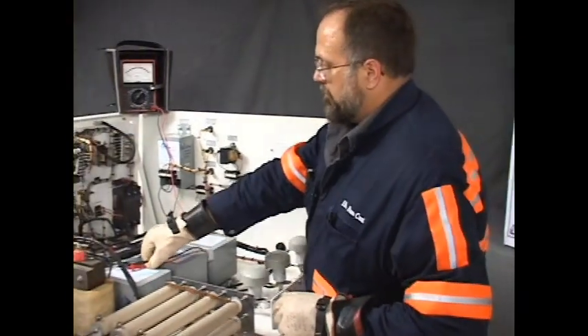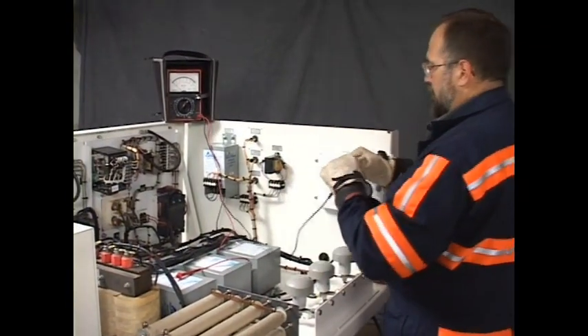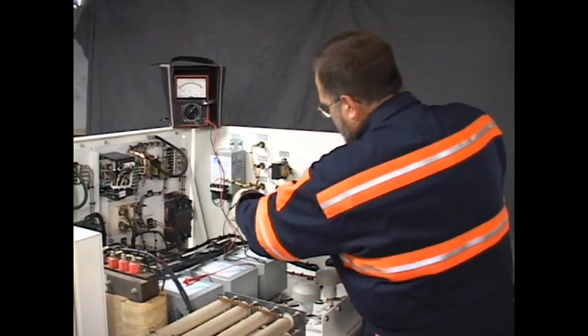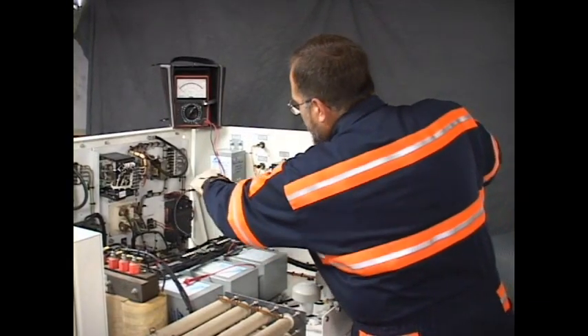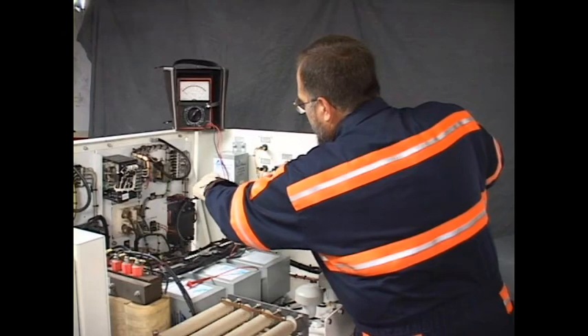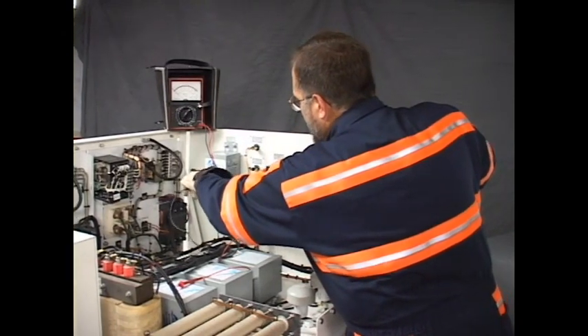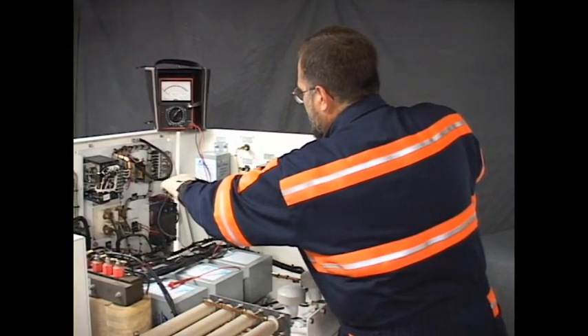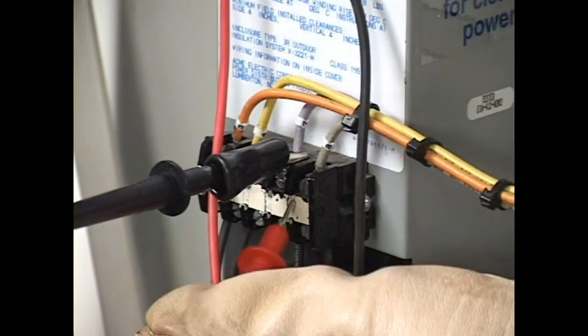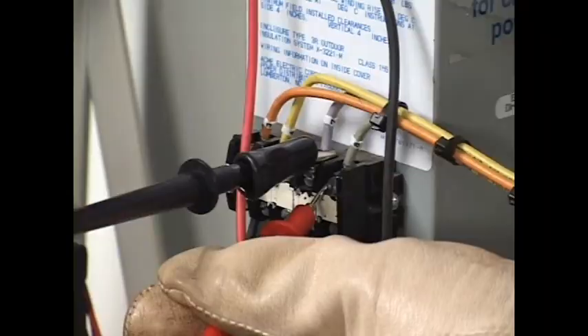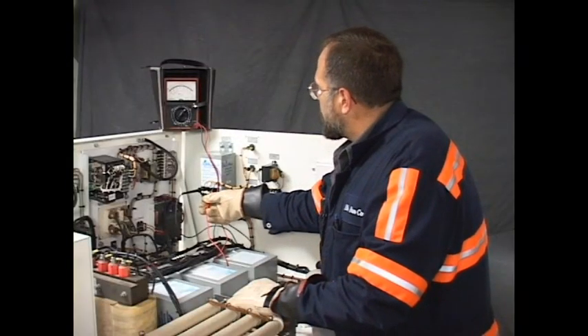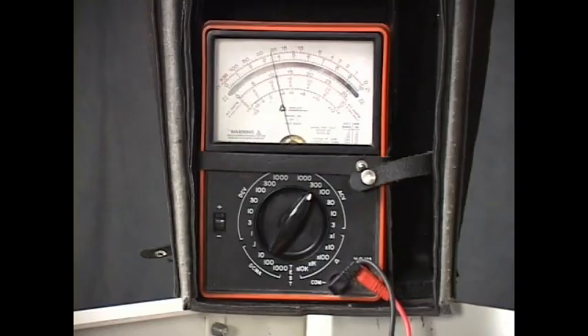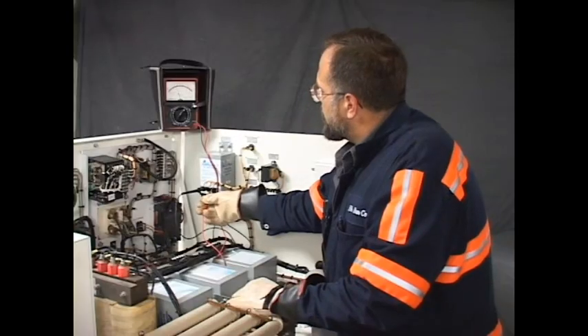I'm going to attach my black probe to that same terminal 7. We've begun there many times today. And I'm on terminal 7. I'll take my other probe and read my control voltage at the transformer. That reads, as you can see, between 110 and 120 volts AC.